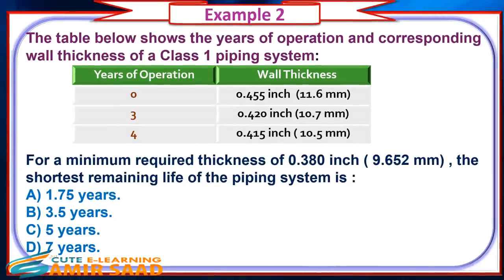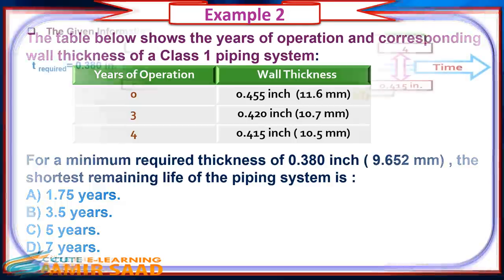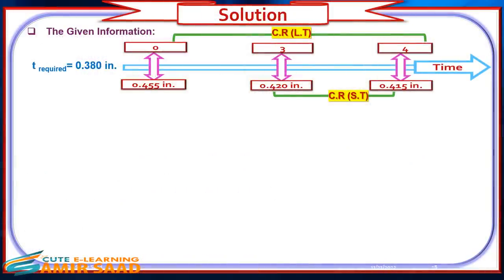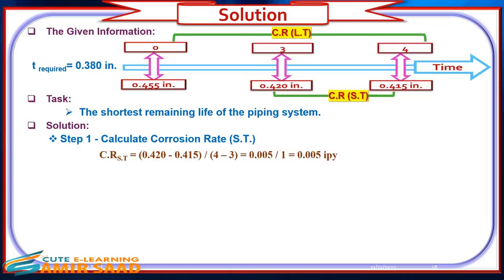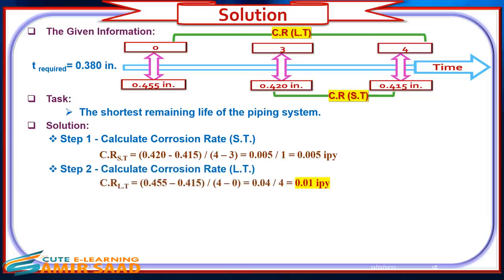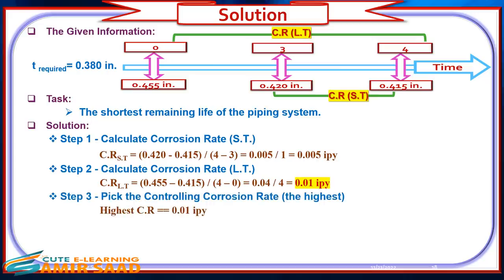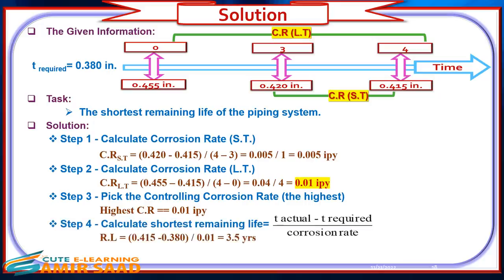Example 2: The table shows years of operation and corresponding wall thickness for a Class 1 circuit with a minimum required thickness of 0.380 inch. What is the shortest remaining life of the piping system? Solution: Step 1: Calculate the short-term corrosion rate. Step 2: Calculate the long-term corrosion rate. Step 3: Pick the controlling corrosion rate — the highest. Step 4: Calculate shortest remaining life. The answer is B: 3.5 years.